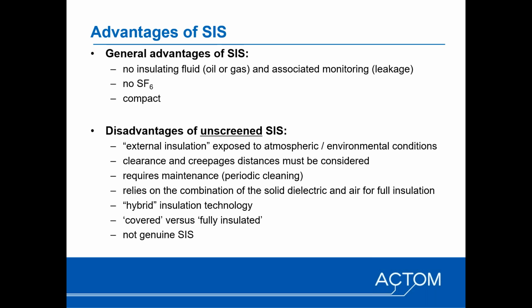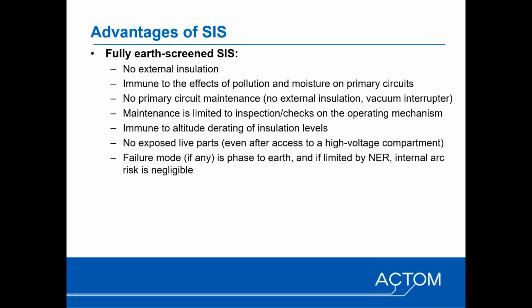It relies on the combination of solid dielectric and air for full insulation. So we would actually say that's effectively a hybrid insulation technology, because the electric field is not restricted to just within the epoxy resin or alternative solid dielectric material. It's a combination of the resin plus the air. It's a bit analogous to talking about a covered conductor versus a fully insulated conductor, or a conductor with insulation applied around it versus a screened cable. And really, in our opinion, that would not be true SIS or genuine SIS, because it is effectively a hybrid solution.